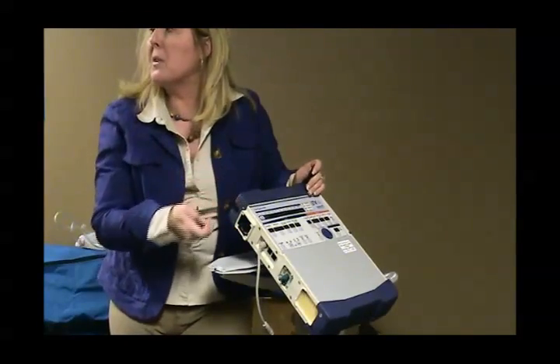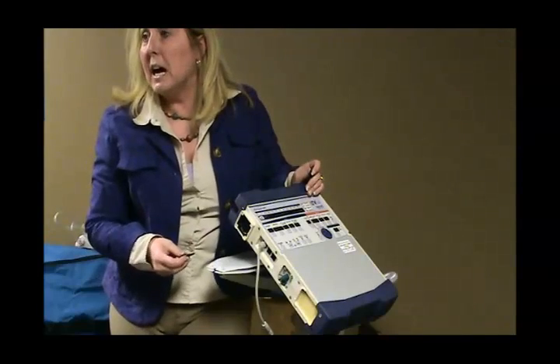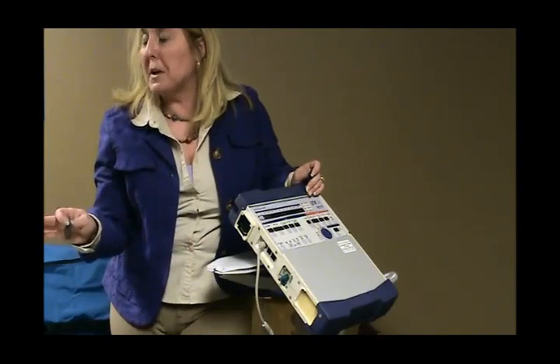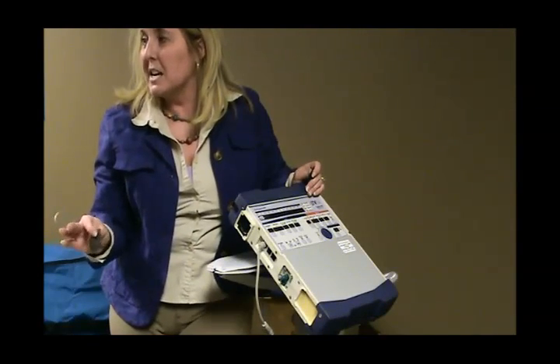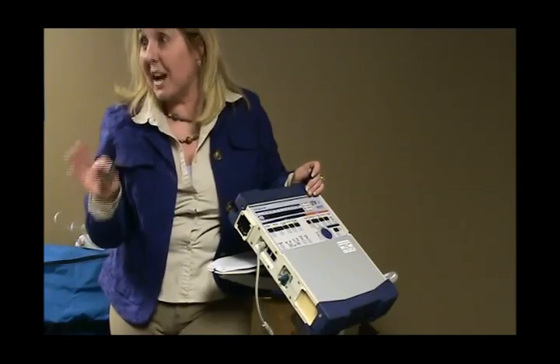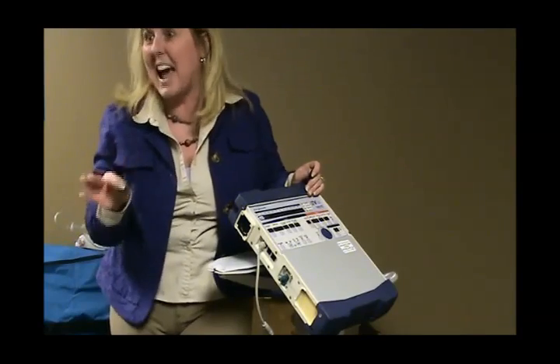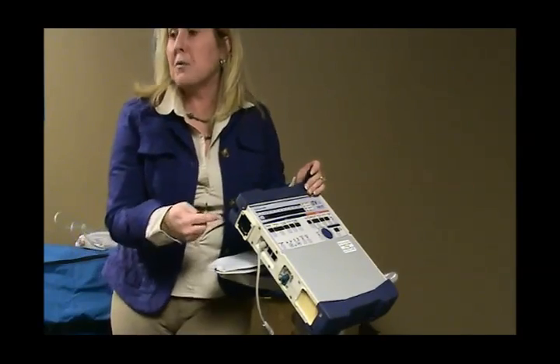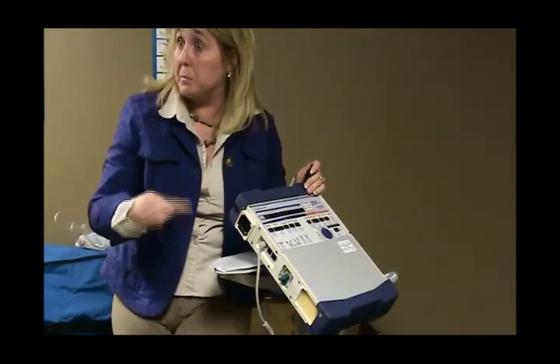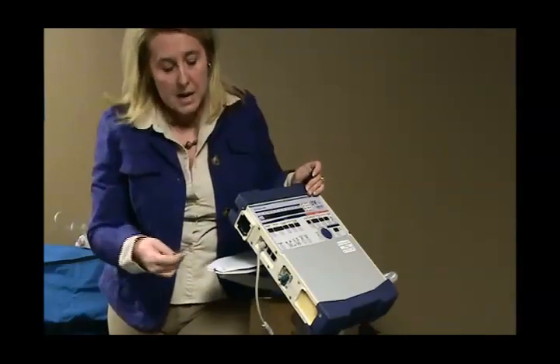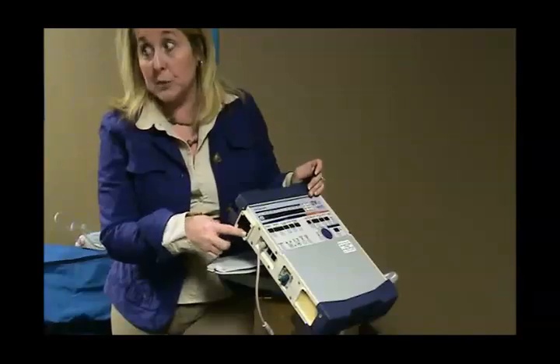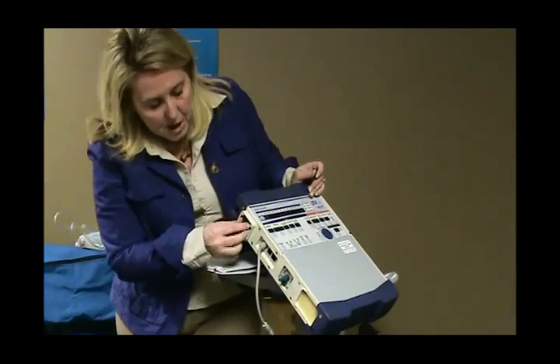If it pops up on the ventilator, hardware fault, if you call the equipment company, the first thing they're going to say is, did somebody stick something in the side of the ventilator? And if they did, get it out. Because it'll stop the fan, and if the fan keeps trying to, it'll burn the fan out, okay? So, remove all foreign objects from the side of the ventilator first.